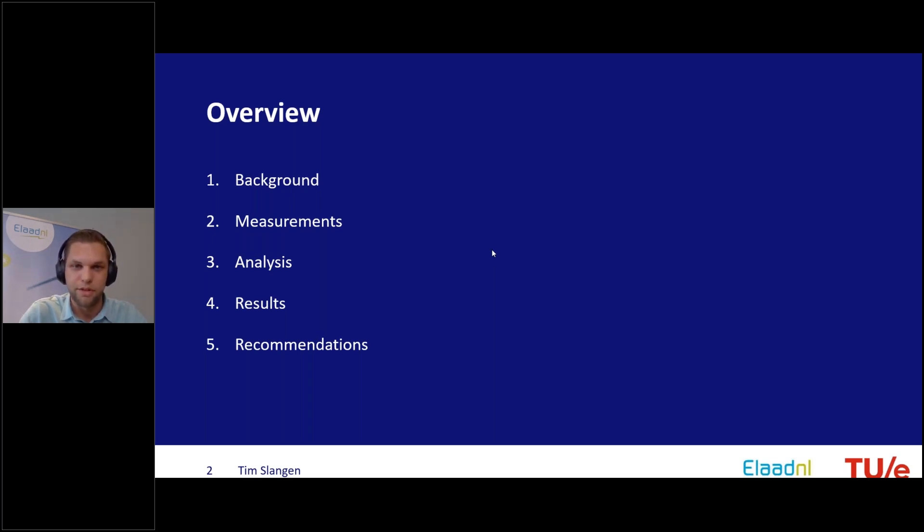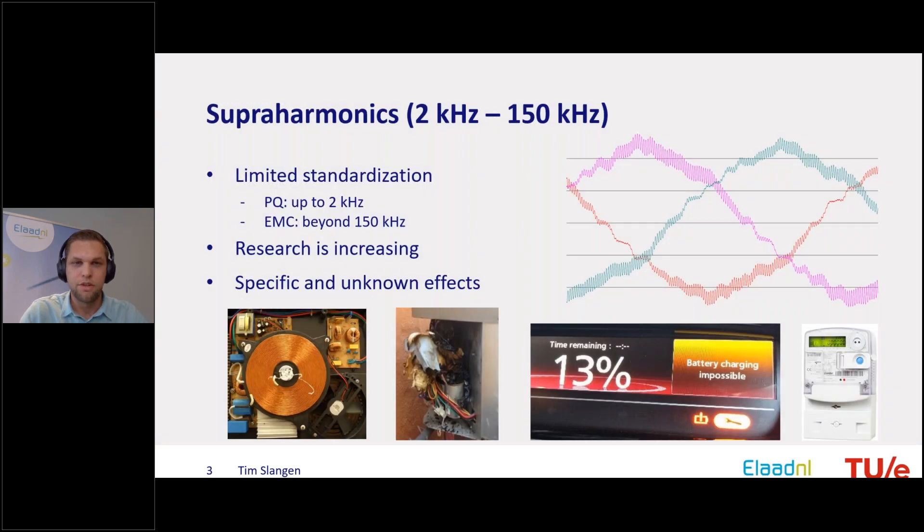I will show some interesting results and conclude with recommendations for further research and for doing field measurements on supraharmonic distortions. Briefly, supraharmonics are conducted waveform distortion between 2 and 150 kHz. This range is somewhat arbitrary, related to the standardization framework for power quality up to 2 kHz and electromagnetic compatibility starting at 150 kHz — beyond that mainly radiated emission. In between, standardization has been quite limited, though there are now some informative standards and research is increasing rapidly.